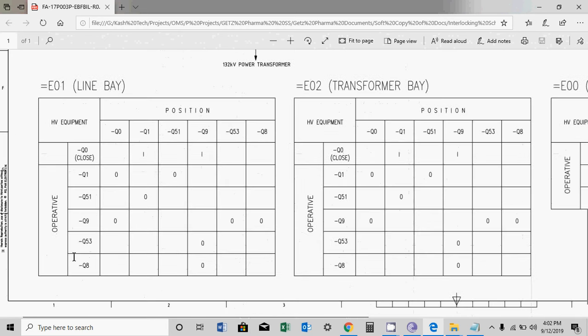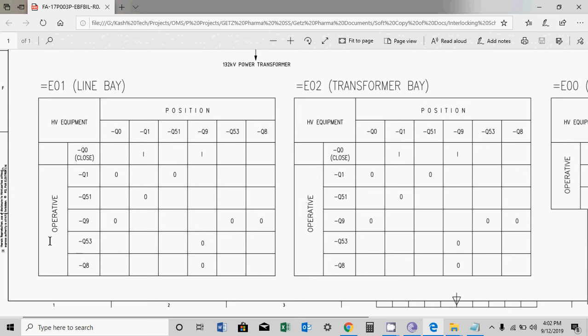Further you will see Q53, it is a built-in earth switch of Q9, so it is mechanical interlock. First you have to open it, then you can close the earth switch. Similarly Q8, you can open it if Q9 is open.